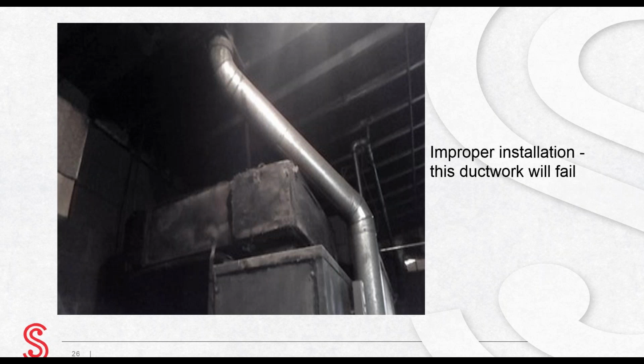Type 1 ducts are constructed of and supported by carbon steel not less than 0.06 inch in thickness, or stainless steel not less than 0.048 inch in thickness. Ductwork and vent piping that are not NFPA 96 Type 1 fail rapidly when they are exposed to heat and fire. This results in the rapid spread of fire and fire damage.